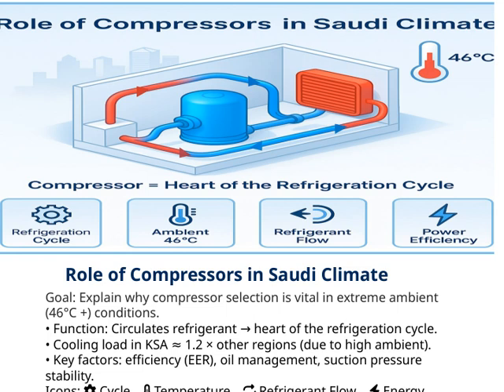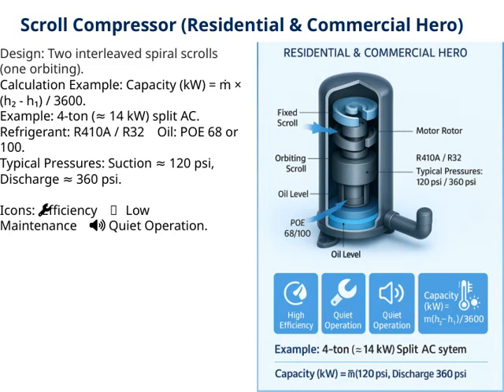Let's get started. Today, I want to highlight the scroll compressor, which is often considered the hero in both residential and commercial HVAC systems. The key feature here is its design, two interleaved spiral scrolls, with one orbiting the other. This unique design allows for smooth, quiet operation and high efficiency. When it comes to calculating capacity, we use a simple formula. Capacity in kilowatts equals the mass flow rate times the difference in enthalpy between the inlet and outlet, divided by 3600. This helps us size systems accurately.